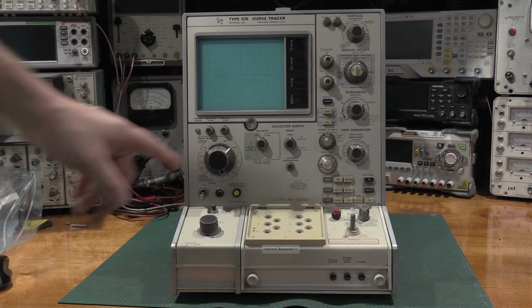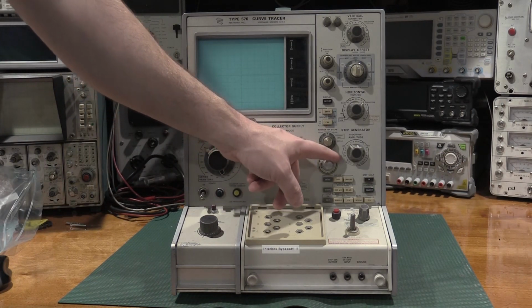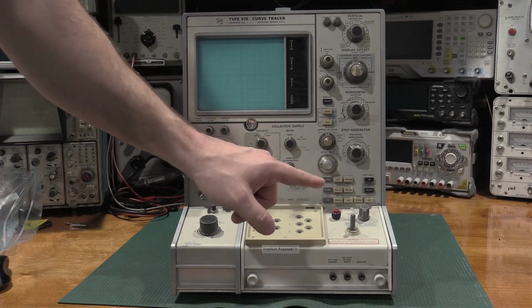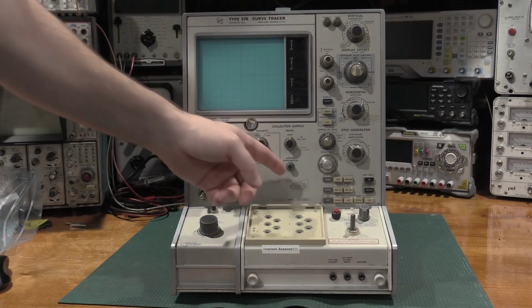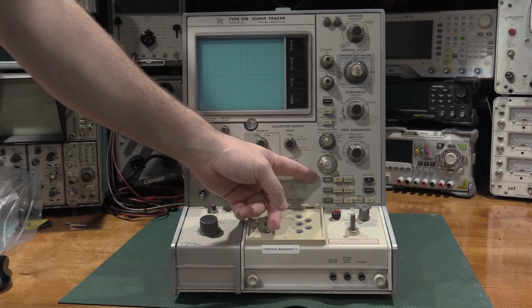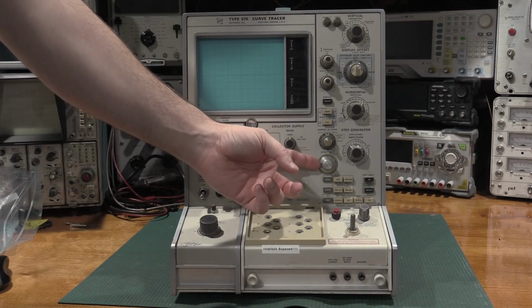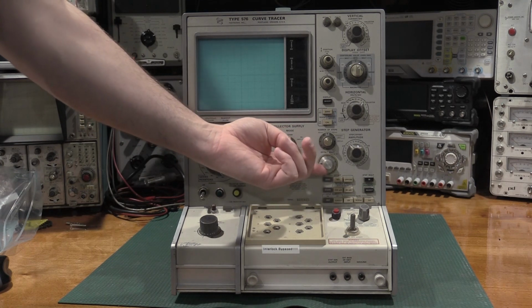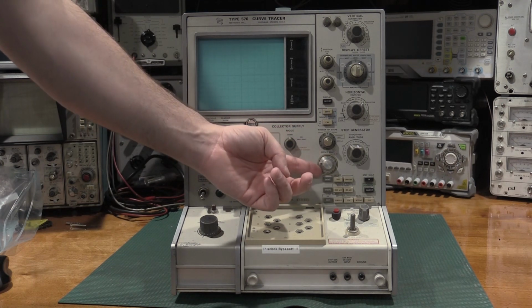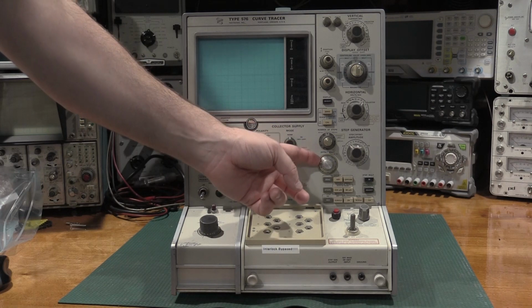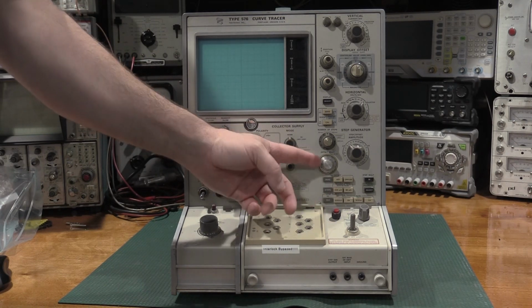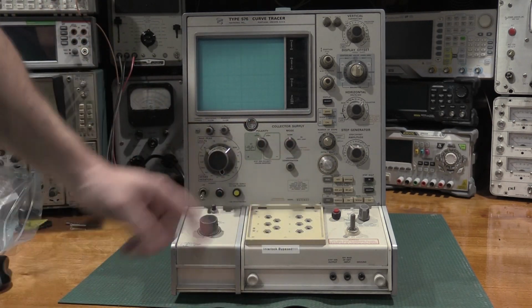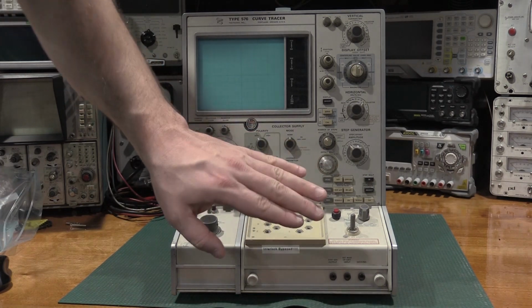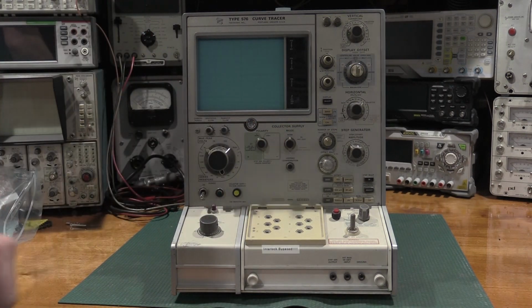This ring is kind of a pain in the butt. Be careful with this control here. If you see this is punched in, you're going to have a real tough time getting this control back. The lip of this plastic is what holds the 10-turn pot in. So there's a copper spring on the back of here that kind of holds this in, but then this keeps it from being pulled into the case. If this plastic breaks, that control will fall completely into the case.